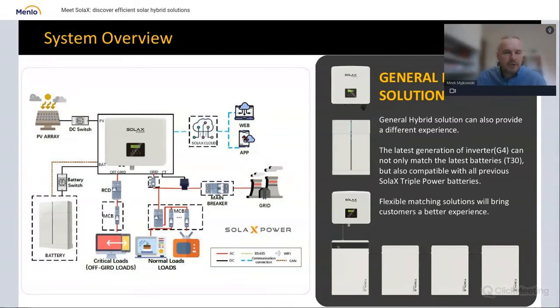Here we have a situation when there are critical loads, backup loads, and normal loads, so we're using the internally built EPS switch. That's how it looks - there's no matebox here, just the simplest layout of the system: battery in minimum amount, the inverter, and the measuring device. Here you can see the CT installed between the main breaker and the inverter breaker.